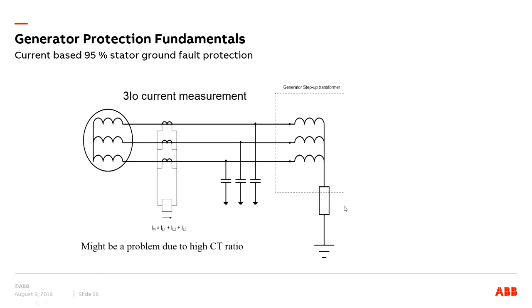There is another method which is called a 3I0 current measurement, where the 3I0 value is measured by the residually connected CTs. And one difficulty with this solution is that the current transformer ratio is normally so large that the secondary residual current will be very small. The residual current due to differences between the three-phase current transformers can be in the same range as the secondary earth fault current. Okay, so that's one possible disadvantage with this scheme.